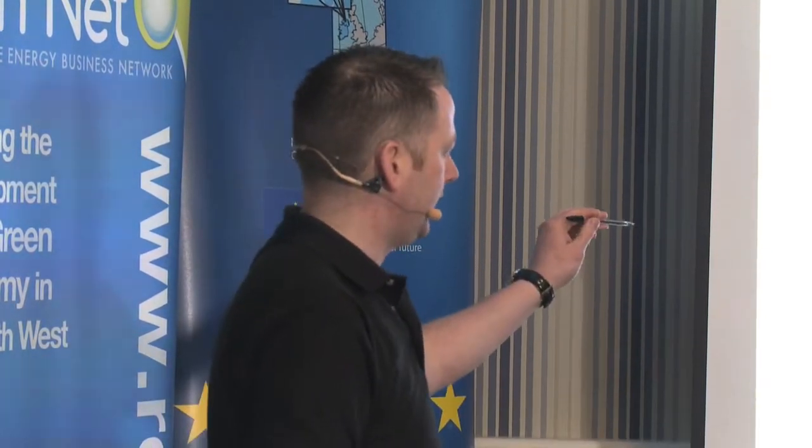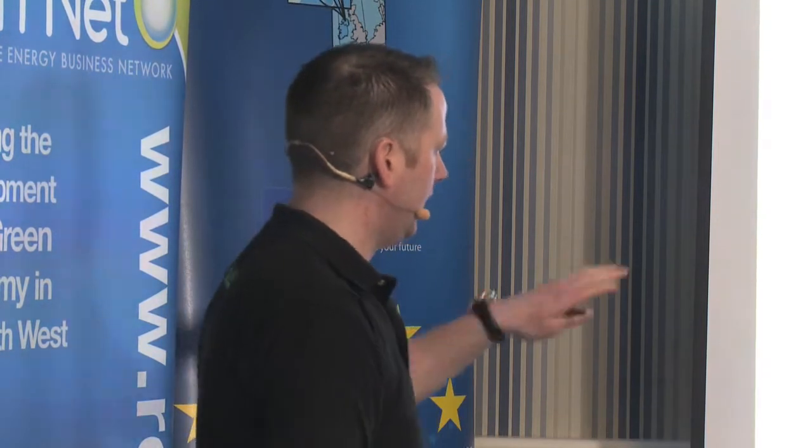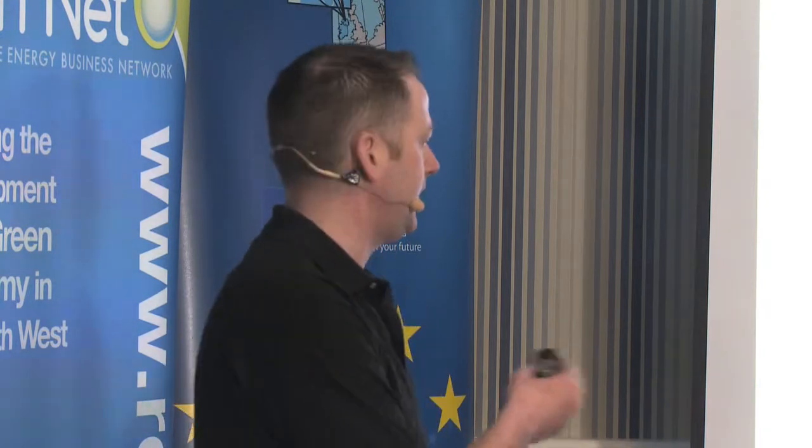you should use a 30 mil strip of insulation around the walls. A lot of people would tend to use the 10 mil strip of expansion joint. But that wall is a thermal mass, and it sucks heat in, and it'll suck the heat down to the subfloor. If your subfloor is poured and your blocks are laid, there's nothing there to separate the block from the subfloor. There's no insulation there. The block goes directly on top of the subfloor. So the heat's sucked by the block down into the subfloor, and you're losing heat there. If you put a thermal imaging camera on that, you'd see that happening.